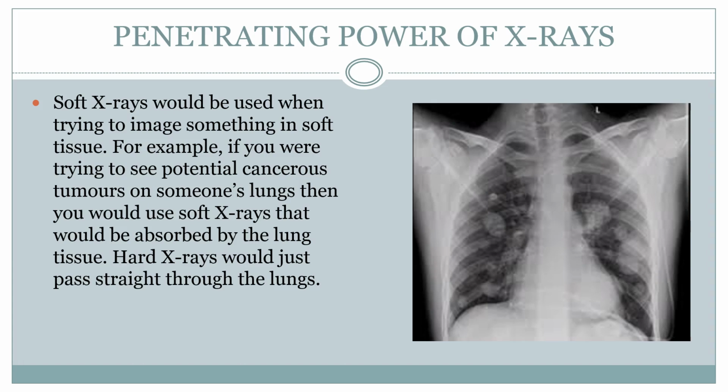Soft X-rays are sometimes also used if the thickness of the material that the X-rays have to pass through is quite thin. So for example, if you're getting dental X-rays, even though you're dealing with teeth, which are fairly dense, I suppose, the X-rays themselves only have to penetrate a very small distance from one side of the tooth to the other. So dentists generally tend to use quite low tube voltages, like 60 kilovolts, which produces soft X-rays.